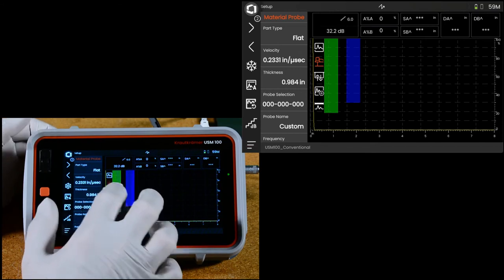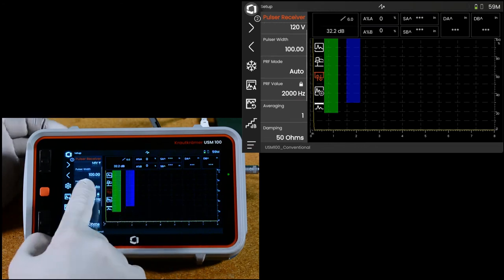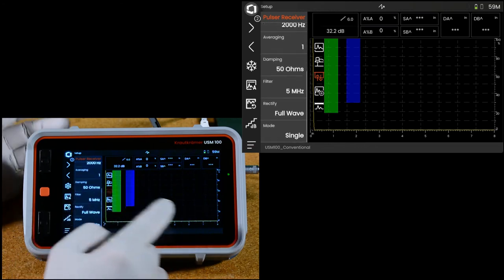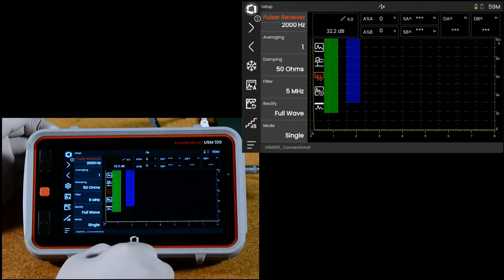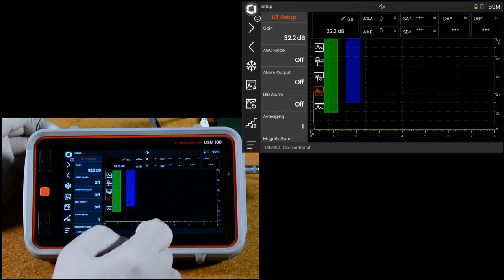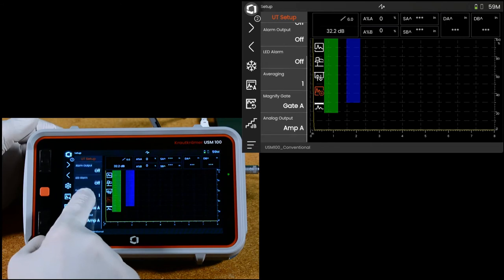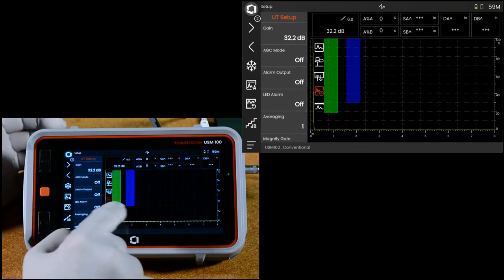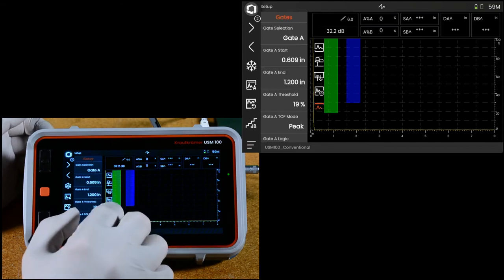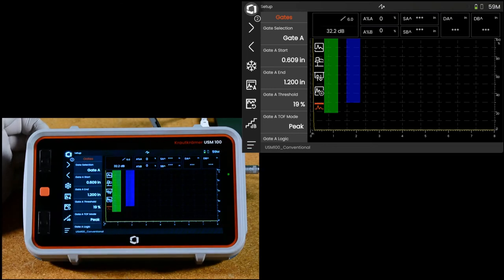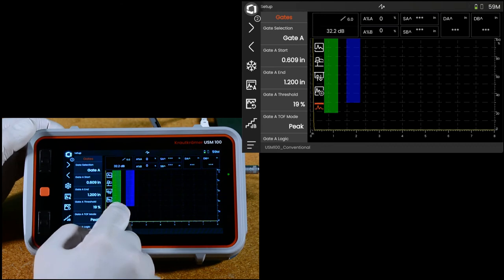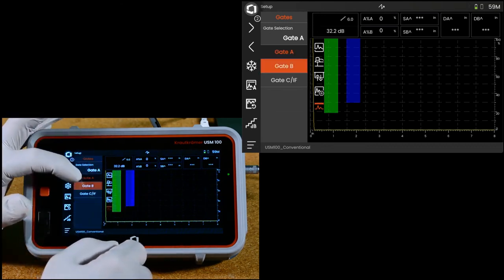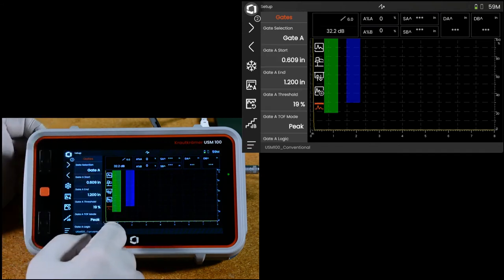Below that is the pulser receiver menu. Pulser voltage, pulse width, rep rate, damping, filters, all the normal selections you would expect for ultrasonic controls. Below that is an A-scan display menu called UT setup. Here you have lots of controls over your inputs and outputs, things like that. Next menu down is gates. And this menu, again, has some context sensitivity. We have one menu for the gates and by selecting gate A, B or C at the top, you get the controls for that particular gate.